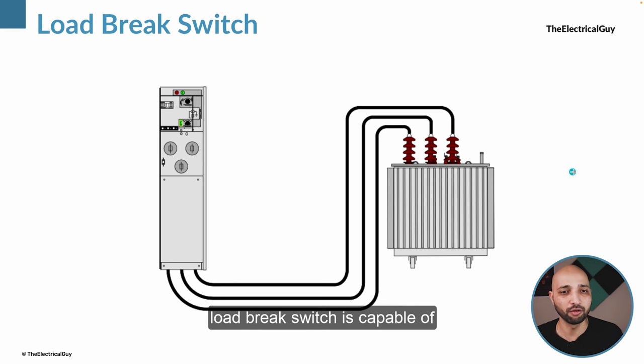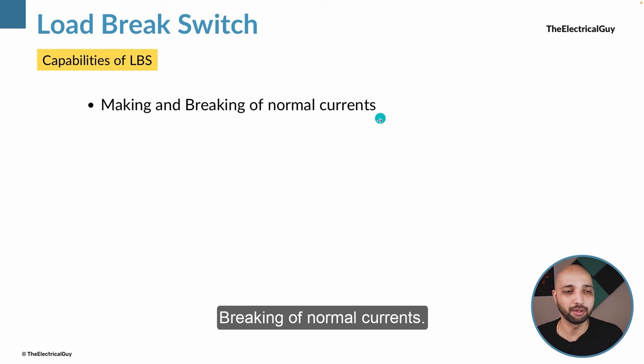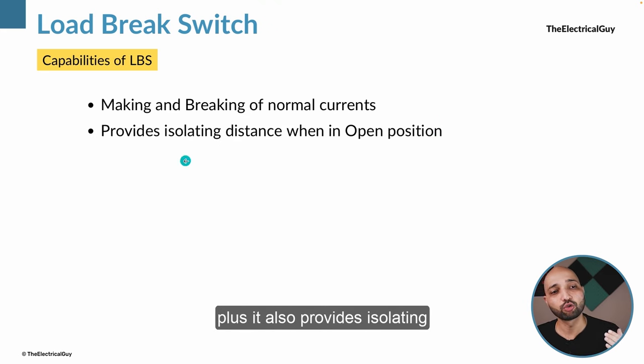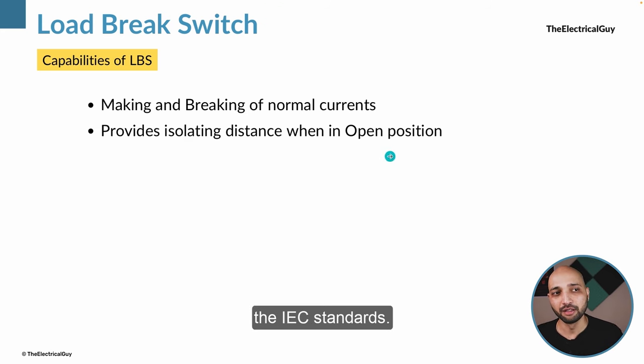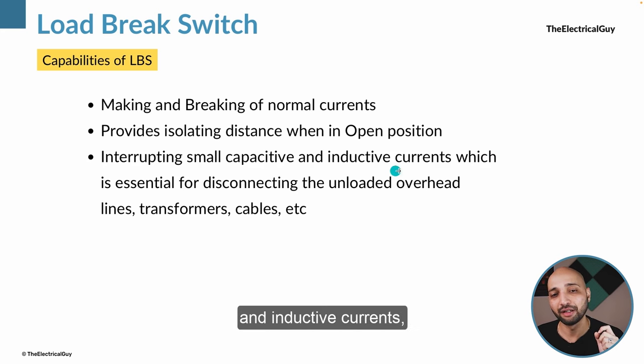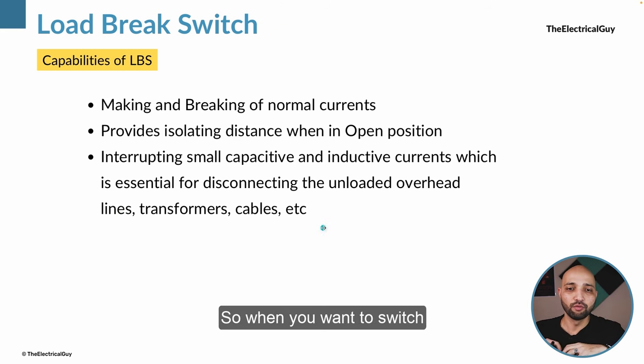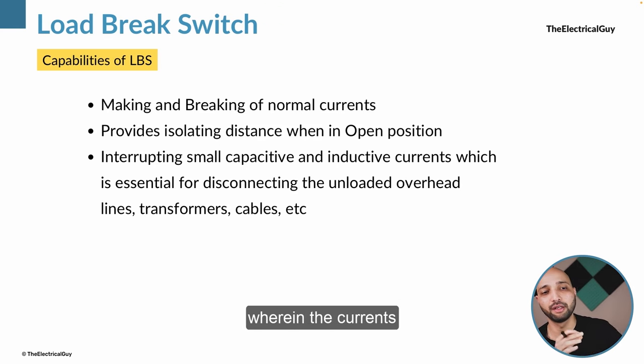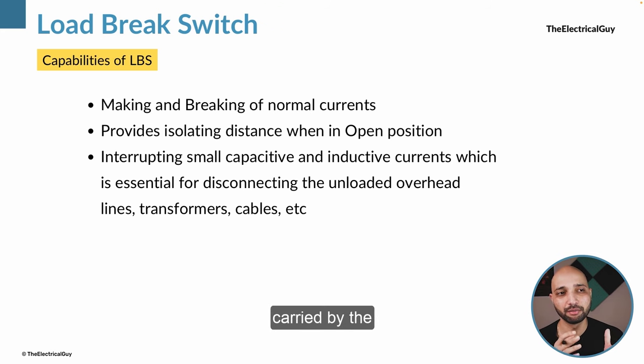Let us look at some of the capabilities of a load break switch. First: making and breaking of normal currents — this is the function of a switch as defined by IEC. Second: it provides isolating distance when in open position, satisfying the requirements of a disconnector. Third: interrupting small capacitive and inductive currents, which is essential for disconnecting unloaded overhead lines, transformers, cables, etc. When switching an unloaded line there will be some trapped charges, and that switching capability must also be present. Similarly for switching an unloaded transformer, where currents will be inductive.